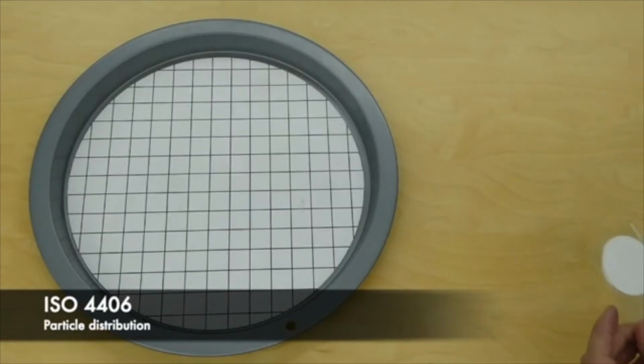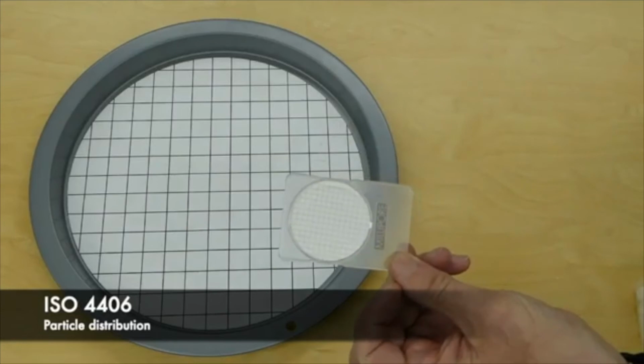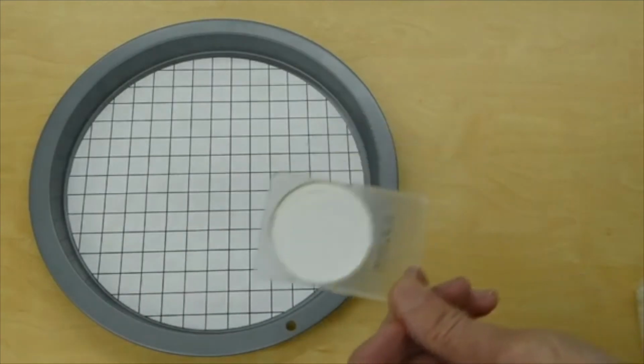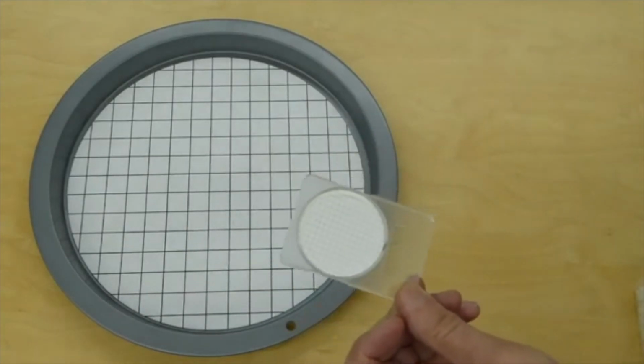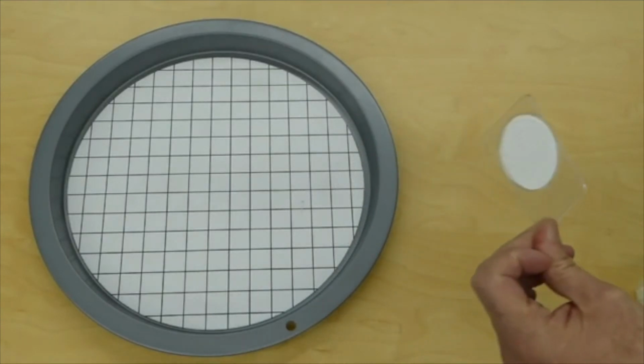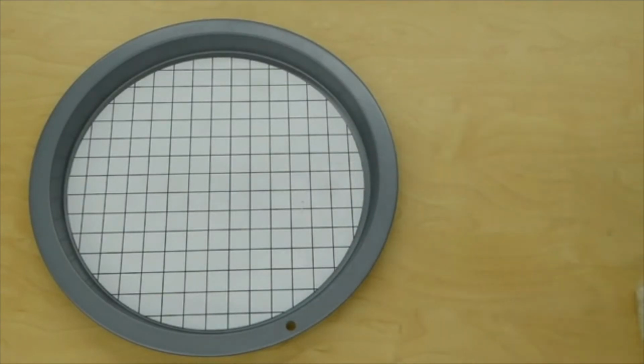What we're doing is taking a sample of oil and pulling it through a membrane such as this one. That membrane is basically going to act like a filter. It's going to remove all of the particles greater than, say, 0.8 of a micron, and it's going to allow us to then place it under a microscope and have a look at that.